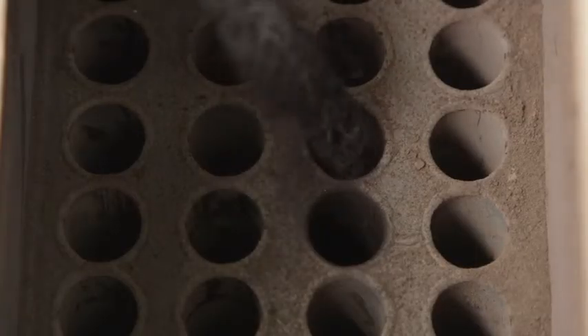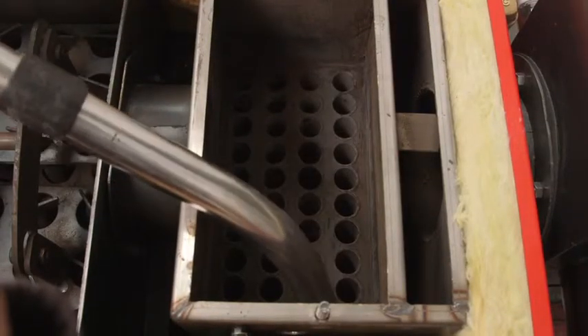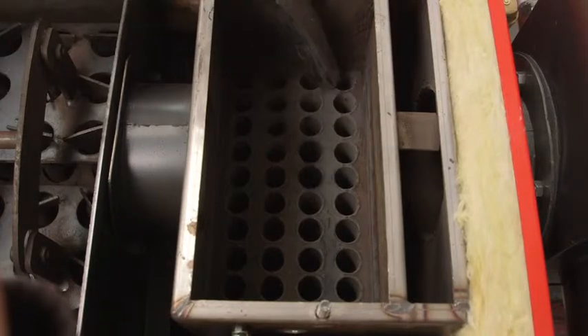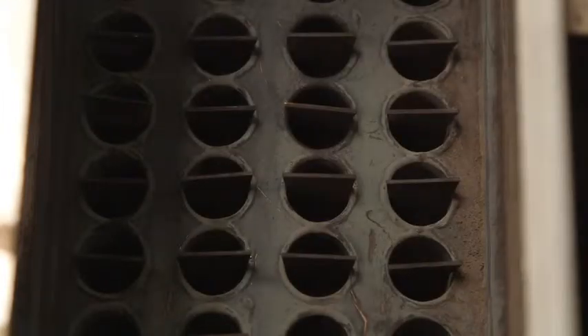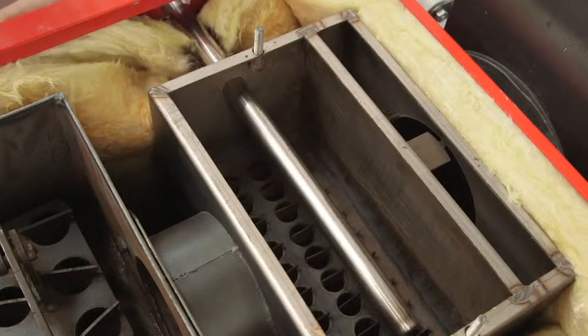Remove and clean the spirals. And clean the tubes using a tube brush. Again, if there is any ash in the top chamber, you should just vacuum it out. When you replace the spirals, line them up so that all the top edges run from front to back. You can now replace the manifold, but don't tighten the screws just yet.